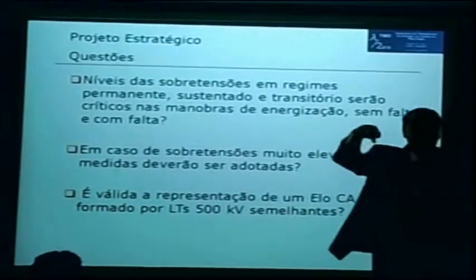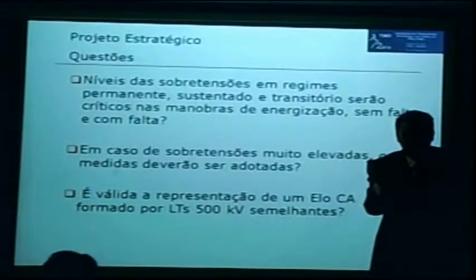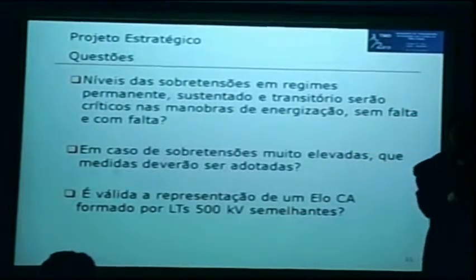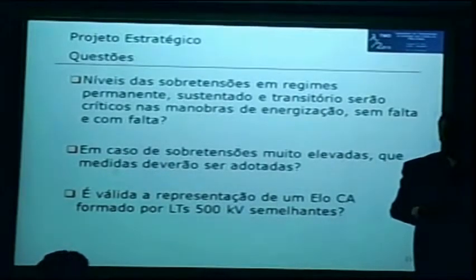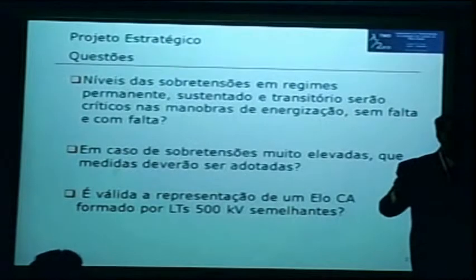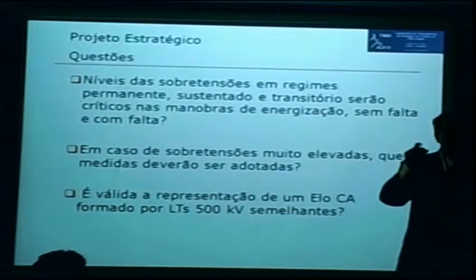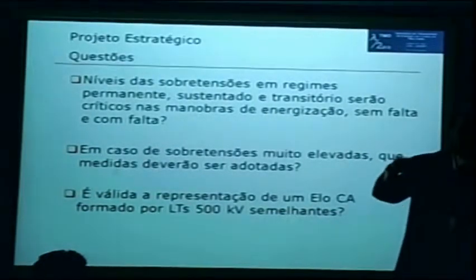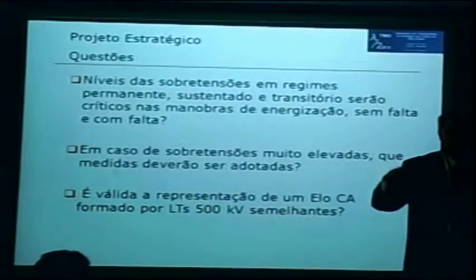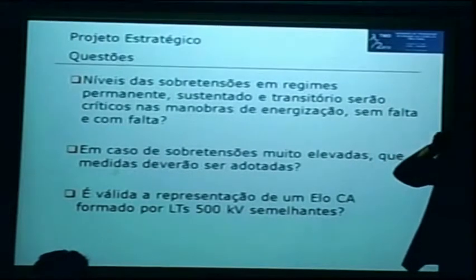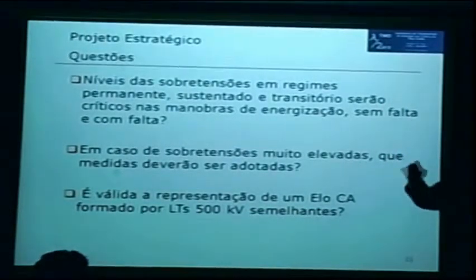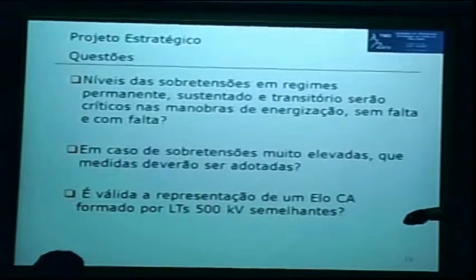One of our concerns about half-wavelength transmission is that when you have a fault in one of the phases at a specific point along the distance, you could have very high overvoltage on the sound phases, and some people are concerned about that. So the question is, can we solve this? Can our R&D propose an alternative, a method we're going to call from now on 'reduced isolating distance', which involves bypassing some insulator chains at a specific point? This is one of the results of this research.